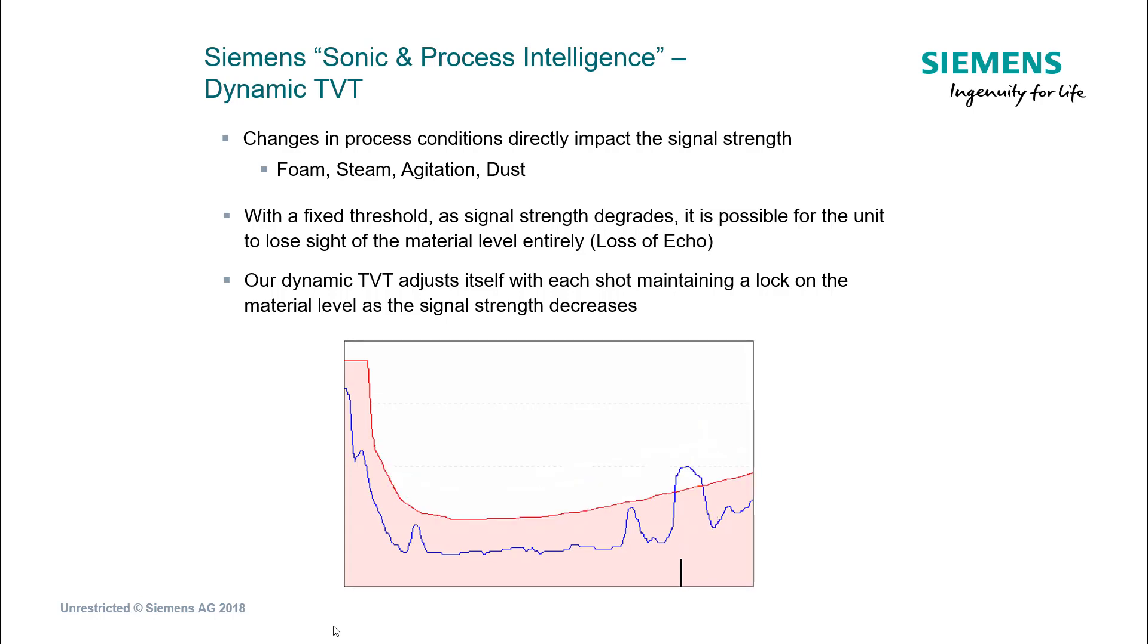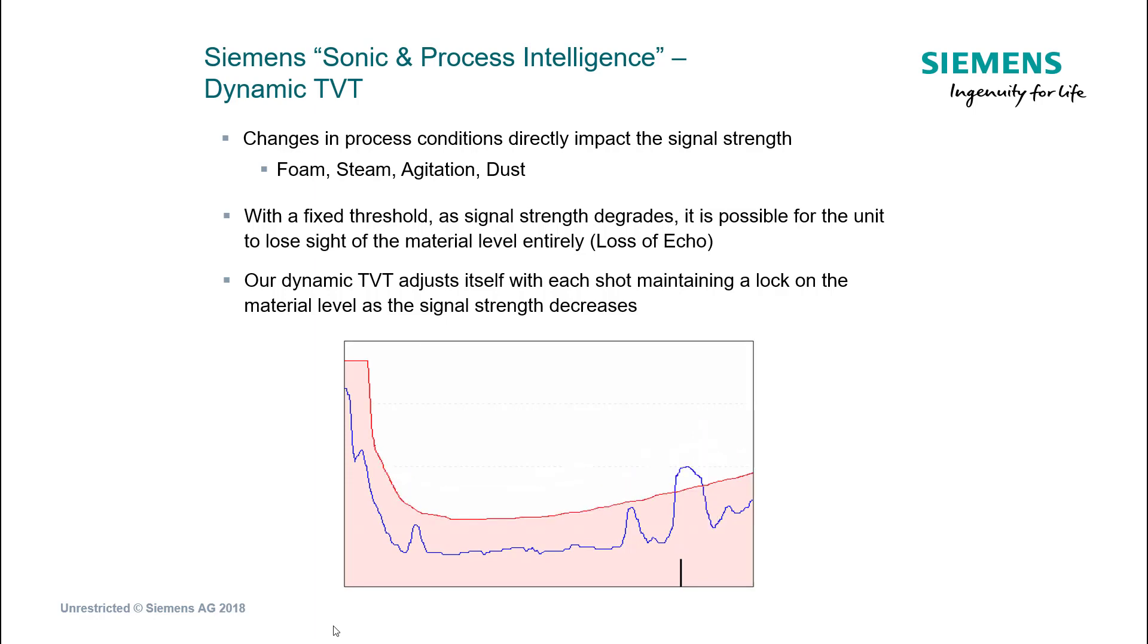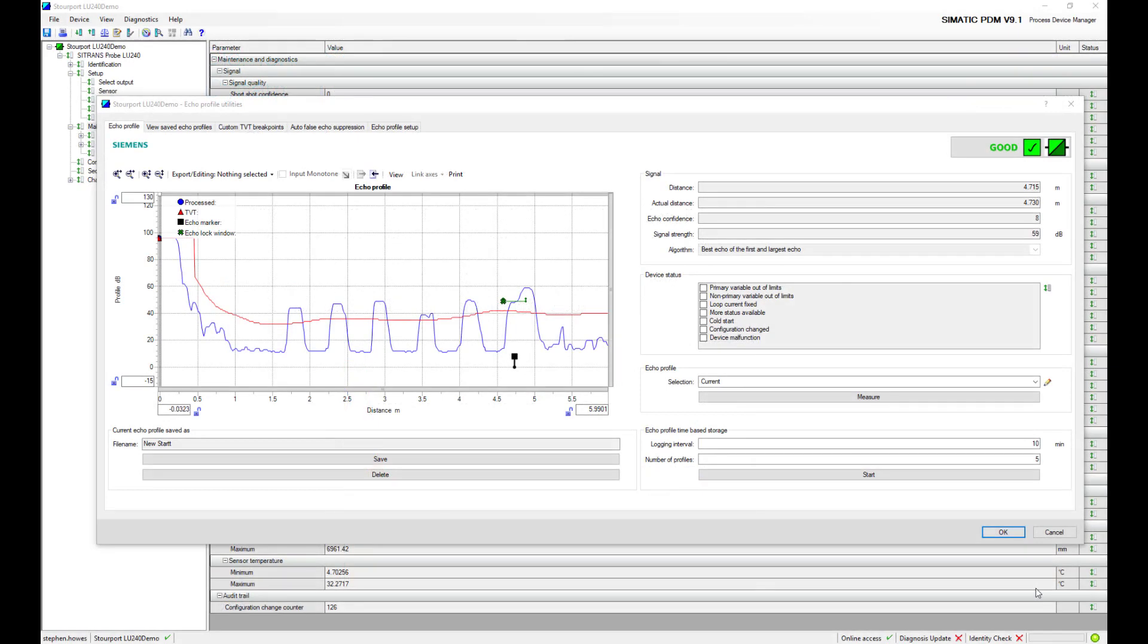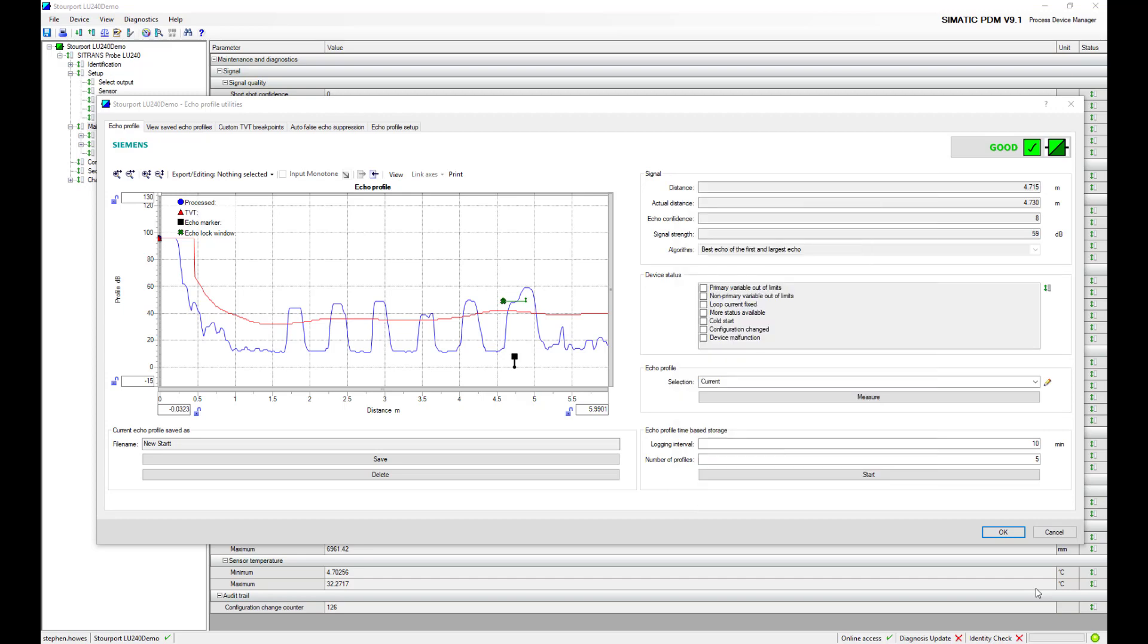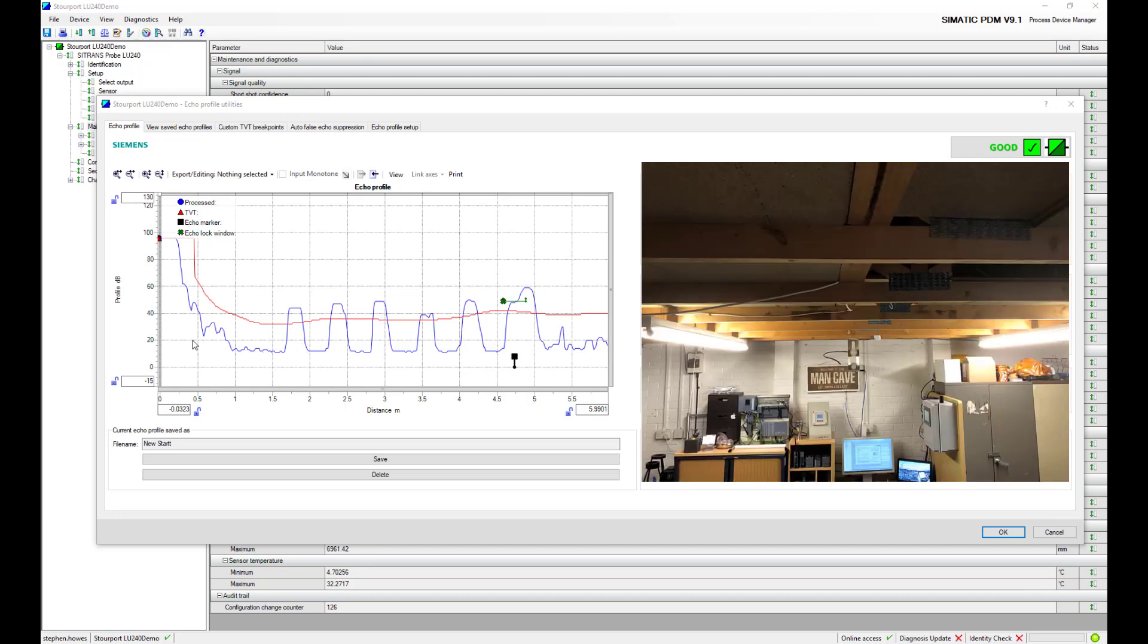Let's start looking at some real life echo profiles from our example. We're going to take a look at the echo profile from the ultrasonic level device which is connected in the man cave. You can see on the right hand side the joists, which are about 600 millimeters apart. We're missing the first few joists purely because the beam angle that's coming out hasn't traveled far enough to hit these first two beams. It's the third beam that we're picking up.